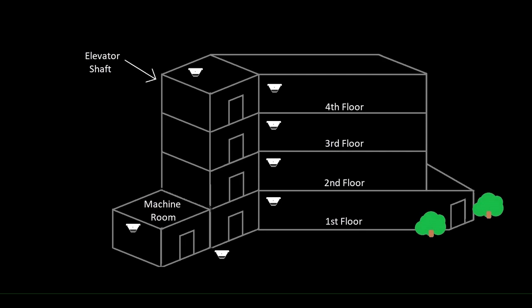So we would turn on the one relay for fire hat flash if, let's say, the machine room activated, but then we would turn on a second relay to send the car up to the alternate floor or down to the primary floor.